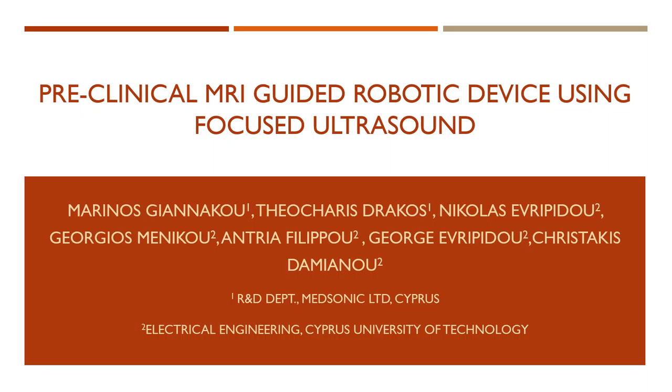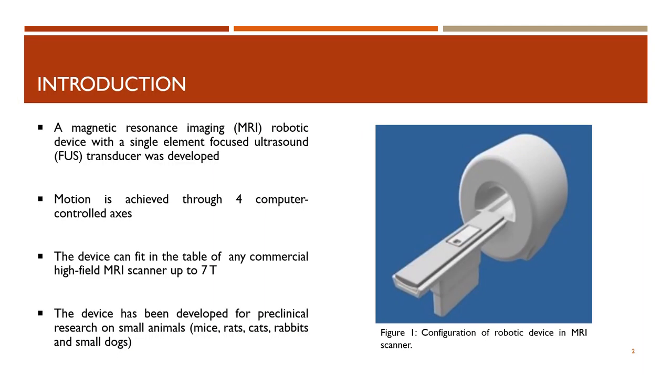Hello, my name is Antria Filippou from the Cyprus University of Technology and I will present to you a preclinical MRI guided robotic device using focused ultrasound. A magnetic resonance imaging robotic device with a single element focused ultrasound transducer was developed. The motion of the device is achieved through four computer controlled axes. The device can fit in the table of any commercial MRI scanner up to 7 Tesla and it has been developed for preclinical research on small animals.